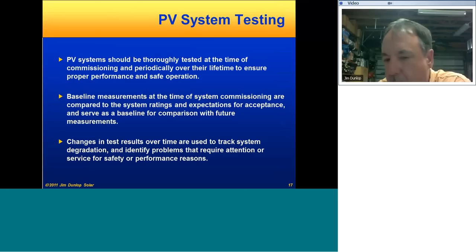These tests are important because they're baseline tests. They give you a benchmark for subsequent tests and expectations that you're going to have later on down the line, specifically for insulation resistance readings. It generally is going to decrease over time, but it's good to know what the baseline is so you have something to compare it against. Same thing with all the other electrical measurements in the system. It's going to help you identify problems and track things down.